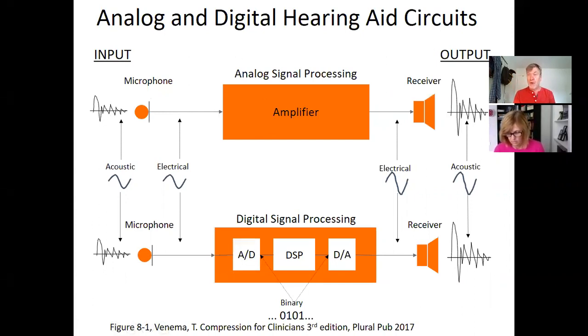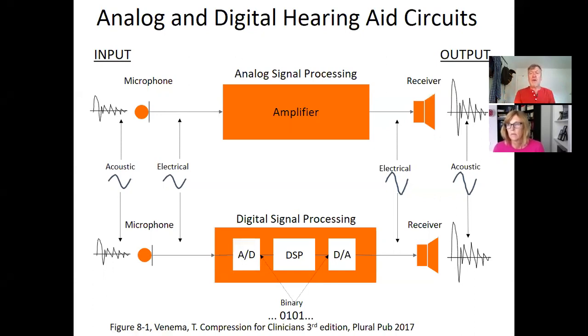ANSI measurements were so highlighted in the old days because they test the hardware of a hearing aid — harmonic distortion, equivalent input noise, reference test gain, output sound pressure level with 90 dB coming in. Now looking at the digital side: there's nothing digital about the mic. A mic is still analog — it changes sound into electricity.